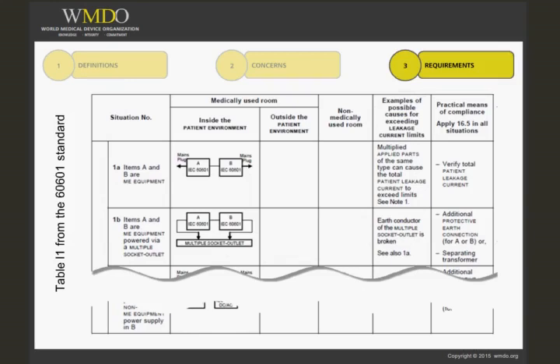Table I1 from the IEC 60601 standard shows examples of medical electrical systems for illustration. It provides a situation and graphically shows whether different pieces of the system are used inside the patient environment, outside the patient environment, or in a non-medically used room. It also gives examples of possible causes for exceeding leakage current limits and the practical means of compliance.